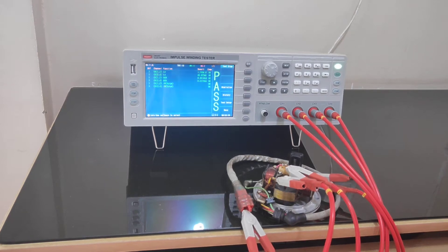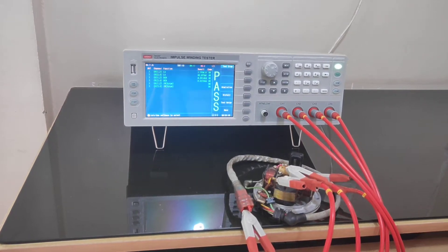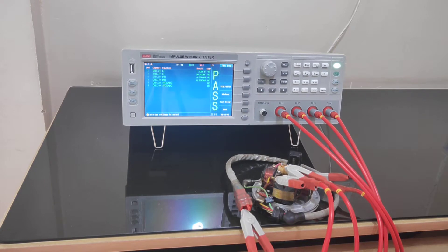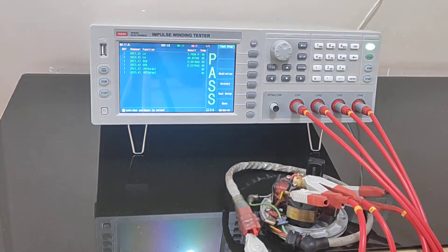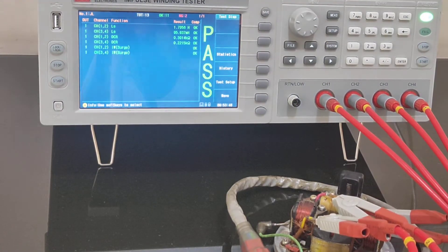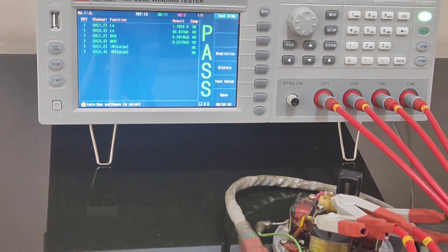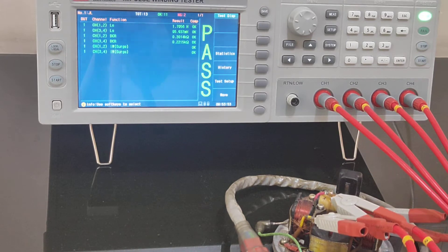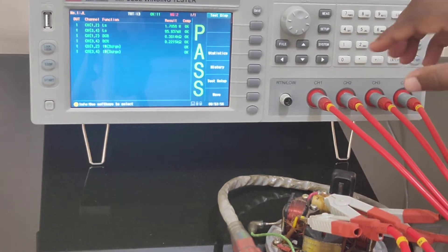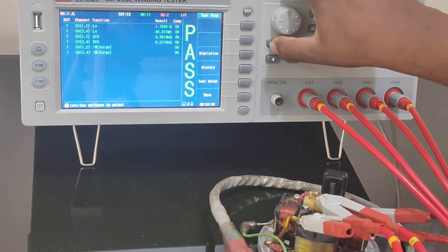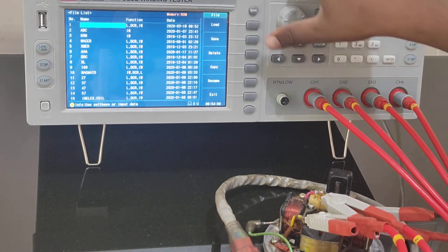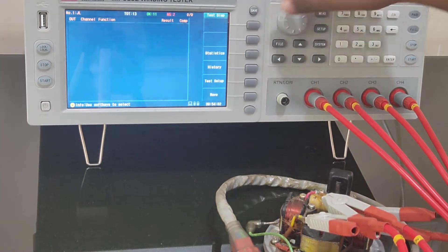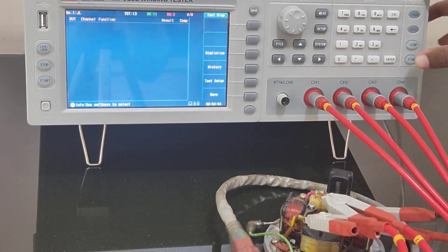This is our new impulse winding tester. With this equipment you can measure impulse winding along with inductance, DC resistance, and it also has a four channel scanner where you can load the predefined test data file, connect the coil and start testing.